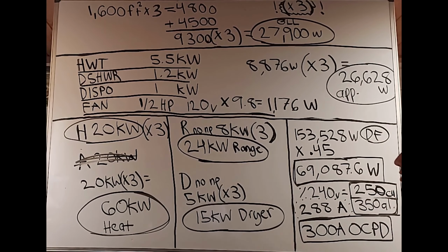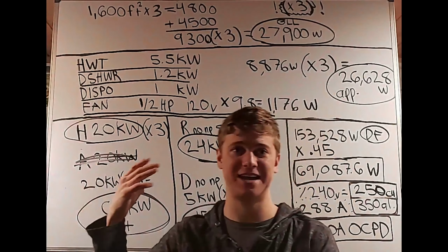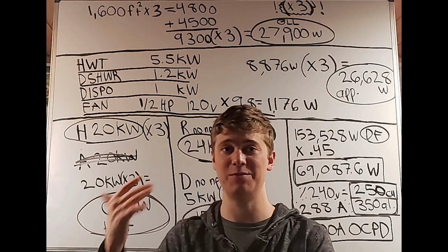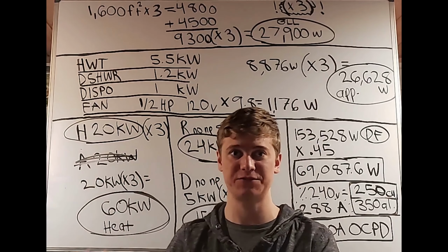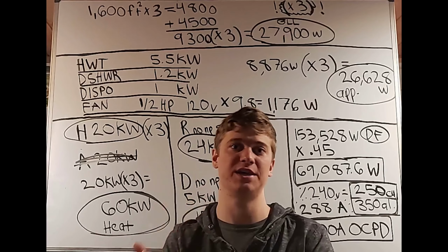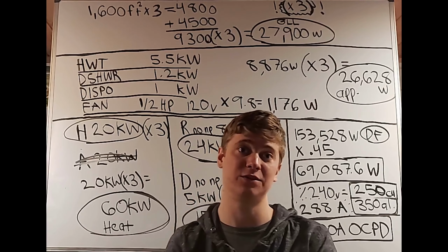Okay, and that's past what you need to know because the question was just asking us what was the overcurrent protection device, and we solved that, and we even took it a step further. Okay, and that's it. You can see it's actually pretty simple. There's not a bunch of demand factors like in the standard method, and it's pretty straightforward here using the optional method for the duplex and also the multifamily.